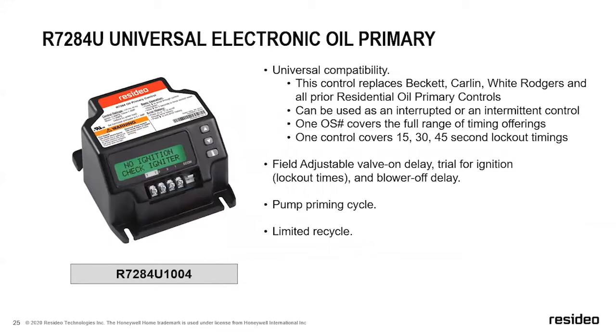So what I would suggest, look at your truck stock now. Are you carrying one for each of those trial for ignition periods? And if so, we can consolidate that down and just carry this one device. And with the digital display, you can program in how long you want that trial for ignition to be. The other thing you can program in is your field adjustable valve on delay. So if you do have a solenoid valve on your oil inlet, you can program how long you want that shut before you want to try for ignition. Your trial for ignition lockout times, which we just talked about. And then we also have a blower off delay. So once I satisfy the heat, how long do I want to continue to run with that oil valve shut?